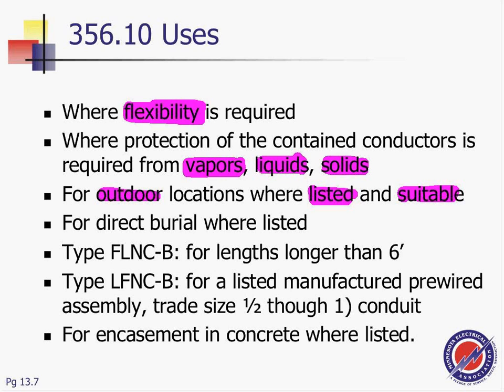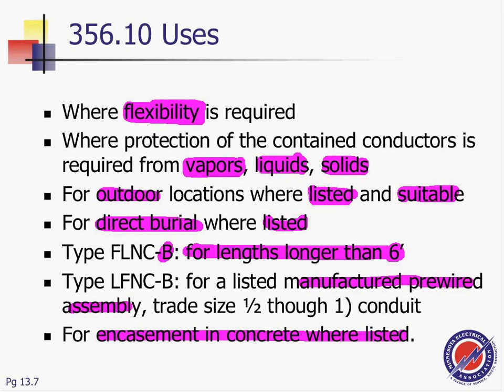But outdoors, can I directly bury it? Bring it on. It's listed, and they list them to be buried directly. You can use more than 6 feet of it for type B only. You can use type B for more than 6 feet, and for a listed, manufactured, prewired assembly in the trade sizes. So those are the uses. I can use type B for more than 6 feet, and I can also use it as a manufactured, prewired assembly. Can I embed it in concrete and encase it? No problem. Look at the applicability of that one.